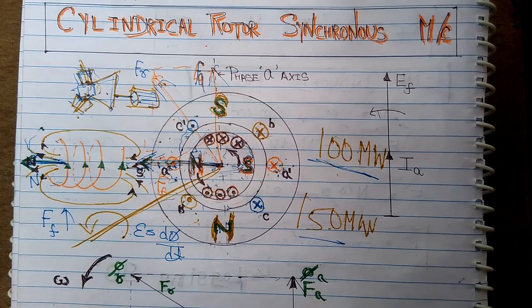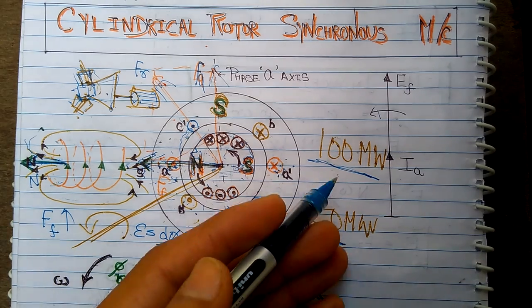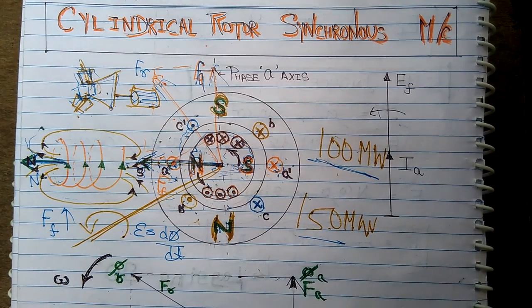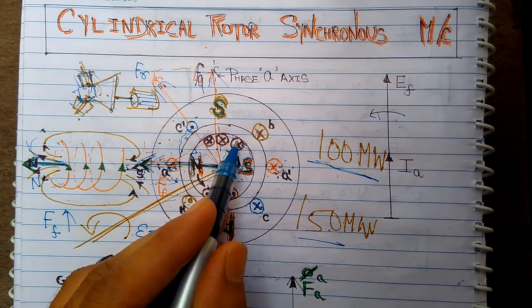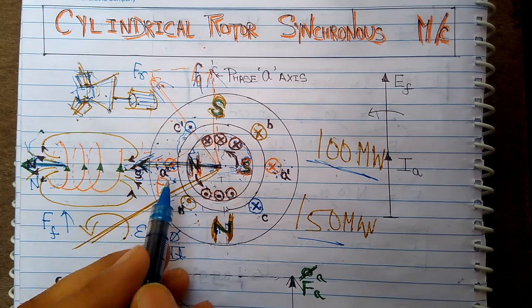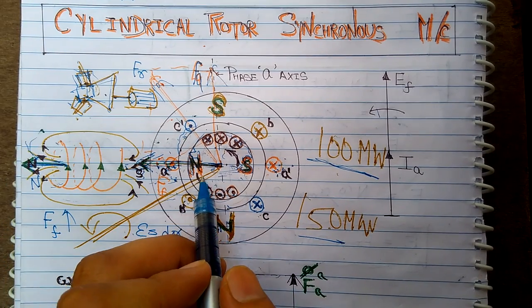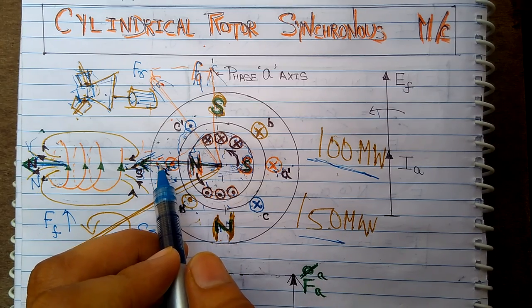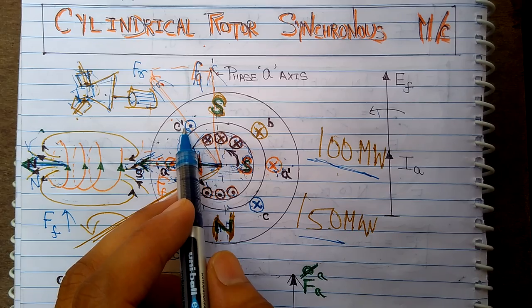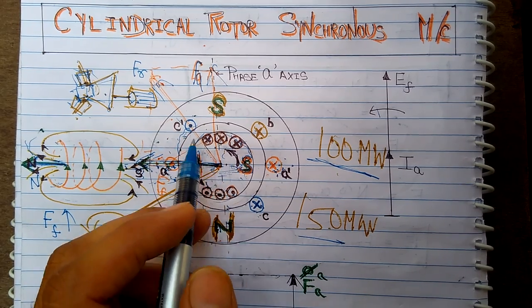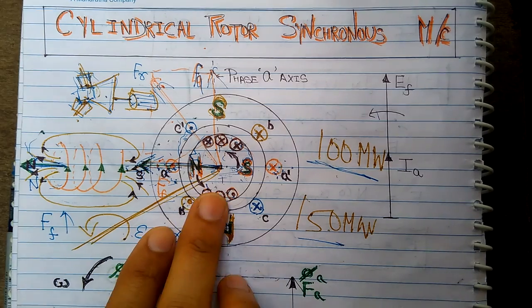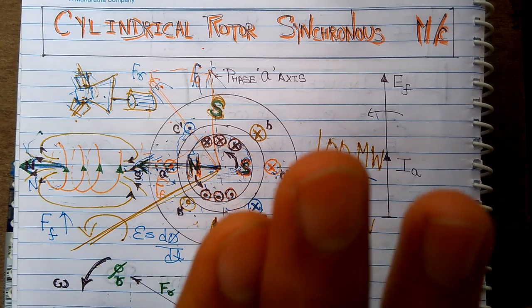Now we jump to our main topic: the cylindrical rotor synchronous machine — an alternator in a power station. What I have drawn is: this is my rotor, this is my stator, these are my rotor windings (dot here, cross here), and these are my stator windings — I call them armature windings. In a synchronous alternator, the field winding is placed on the rotor, not on the stator, while the armature winding is placed on the stator because armature windings carry high current, so it is better to put them on a static part, not on the rotating part.